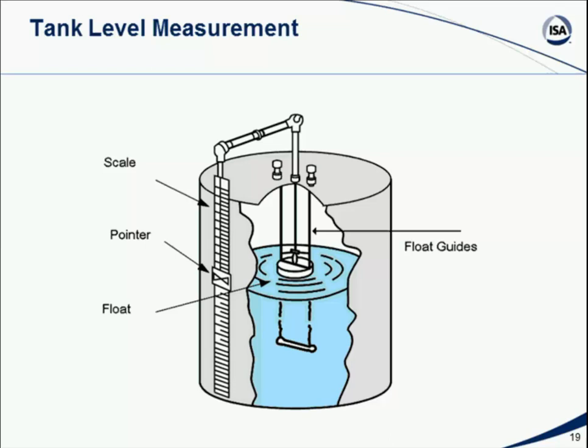And there are quite often guide wires inside the tank that make sure the float isn't bobbing all over the place. But essentially, this is the kind of scheme you're just talking about, this float and cable arrangement. I've got a float in the tank that is guided by some guide wires, but as it goes up and down, the cable from the float goes up through some pulleys, around some piping, and then down to the outside, where it is kept tense by this pointer, which is usually not just a pointer but also the counterweight. So again, as the float goes up and down, the pointer rises and falls, and the scale gives me an idea of what's in the tank.